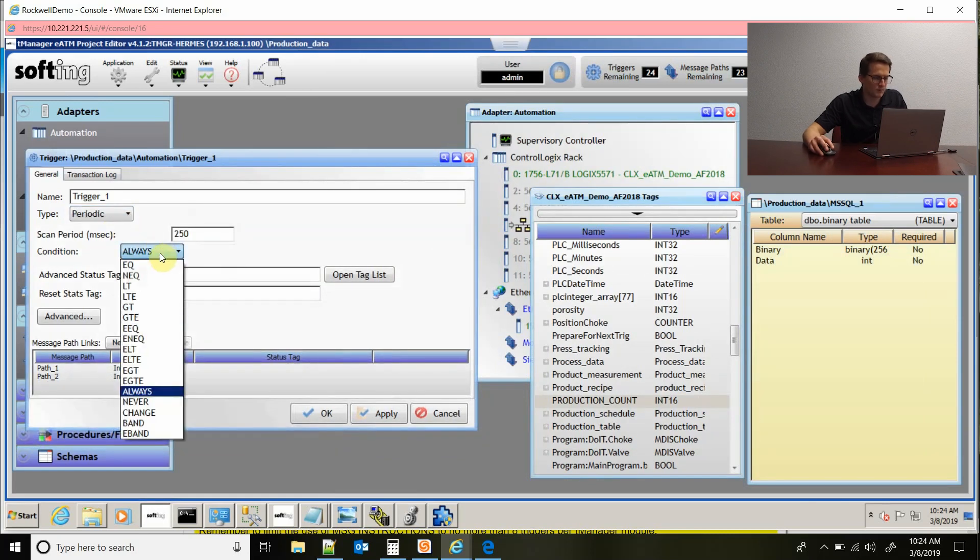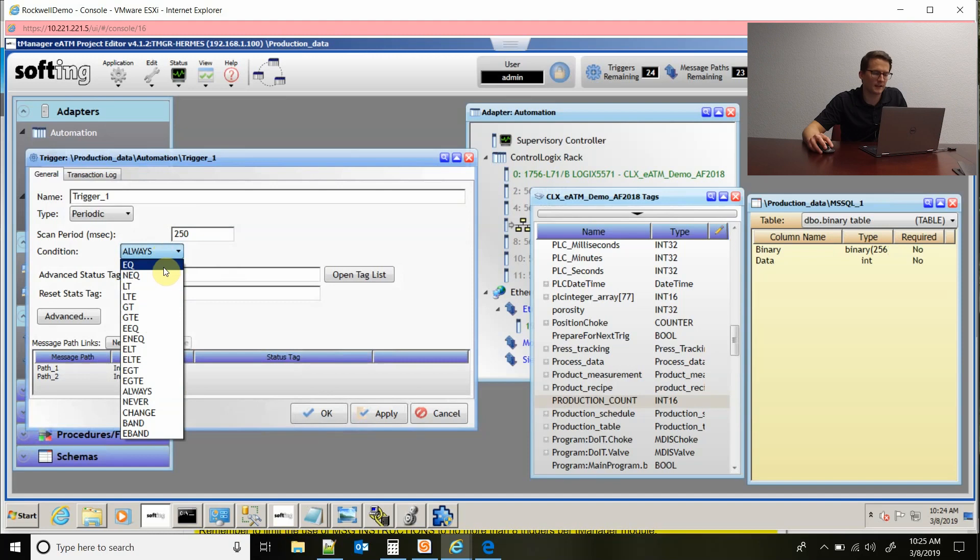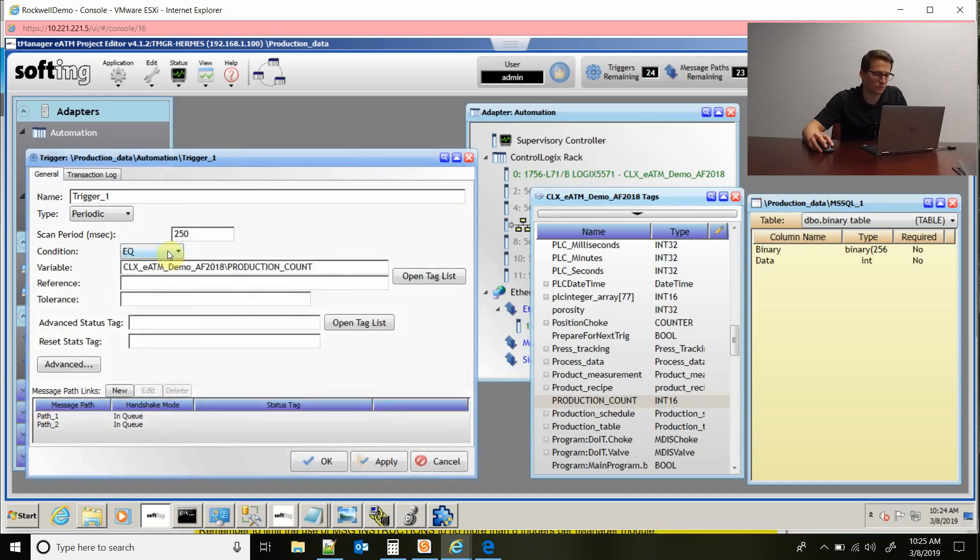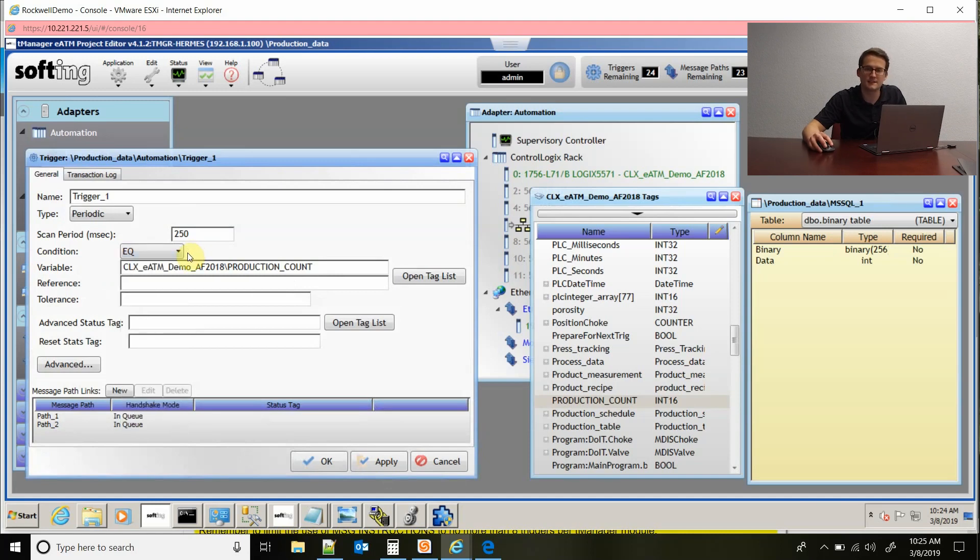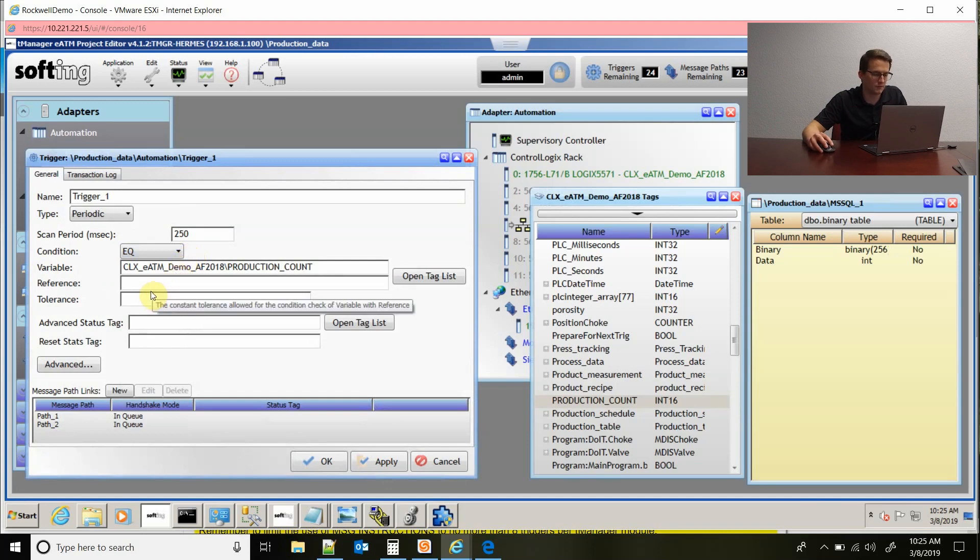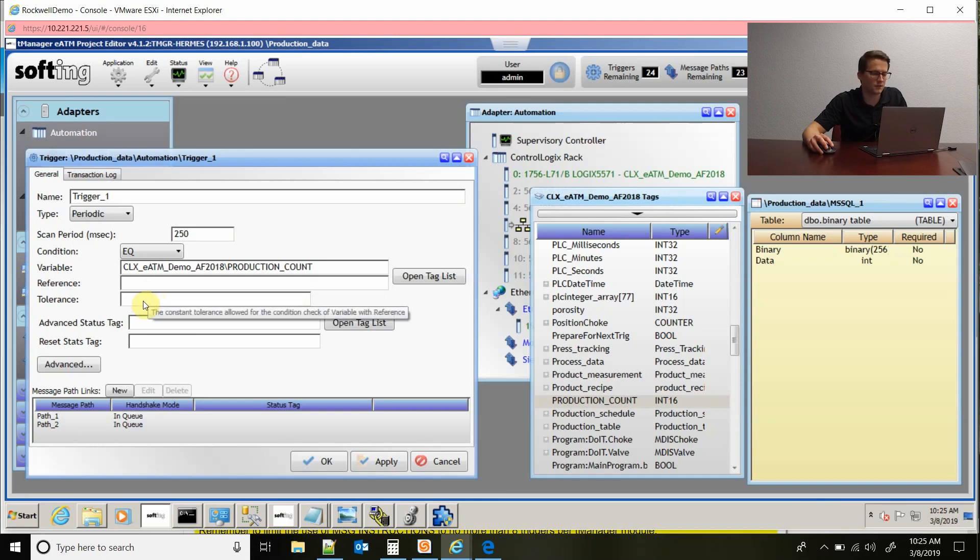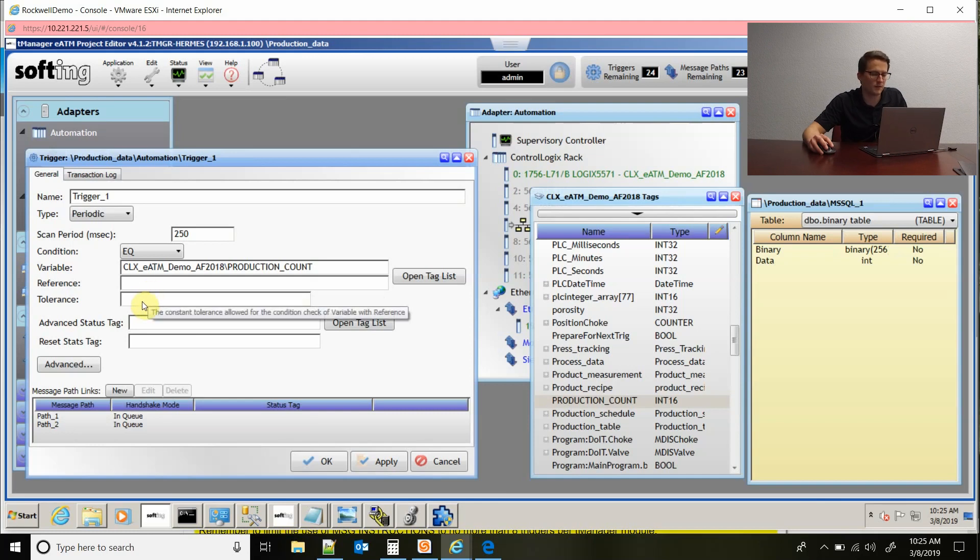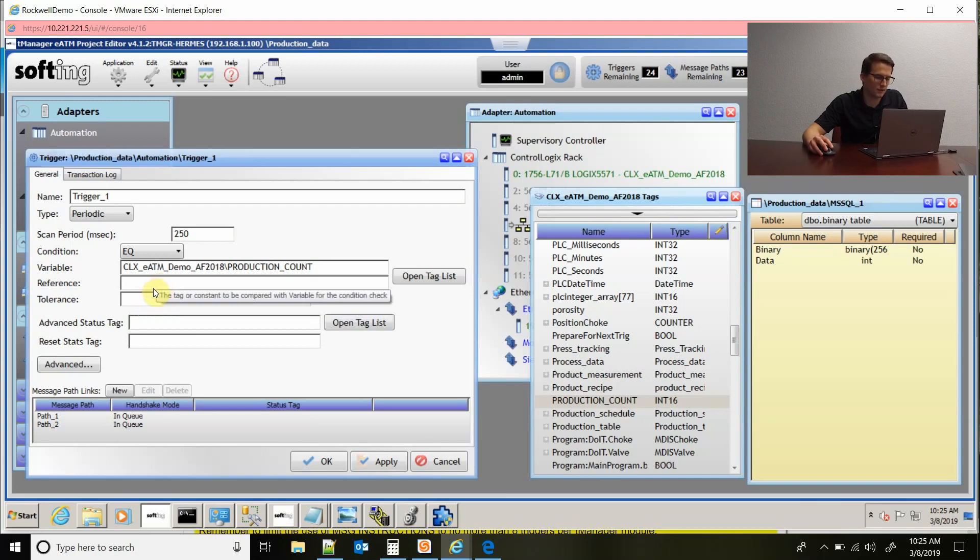I talked about this briefly already, but here's the conditions. You can see there's a big list of them. You could set it equal, so you could set up a tag and set it equal to another tag. You could set it equal to a constant value if you wanted. Or you could set it to where if it's less than something, then it would execute the transaction at that point. There's also tolerance in here. So you could put in a number of one or two, and if it's within one or two of that value being true, it would execute.